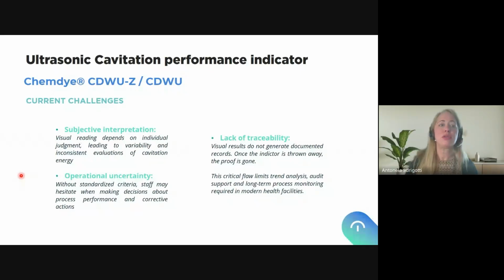What are the challenges of using this type of indicator? The subjective interpretation. Visual reading depends on individual judgment, leading to variability and inconsistent evaluations of cavitation energy. Operational uncertainty. Without standardized criteria, staff may hesitate when making decisions about process performance and corrective actions. And lack of traceability, because visual results do not generate documented records. Once the indicator is thrown away, the proof is gone, and this indicator cannot be kept and documented because it will revert the color. The use is in the moment, and the shape does not make it easy to be kept. Okay, so lack of traceability. This critical flaw limits trend analysis, audit support, and long-term process monitoring required in modern facilities nowadays.